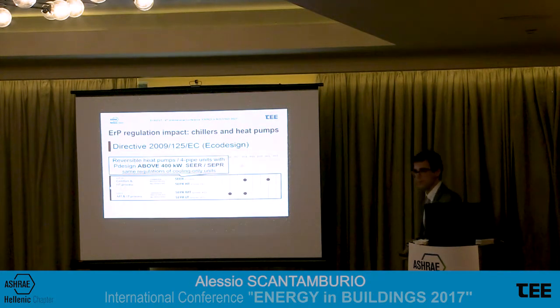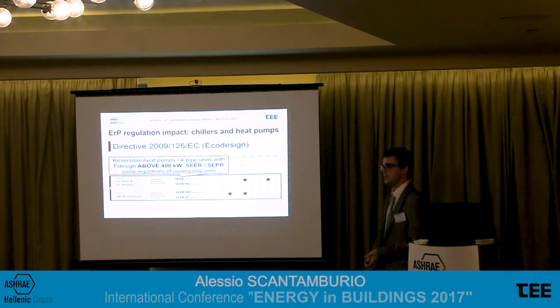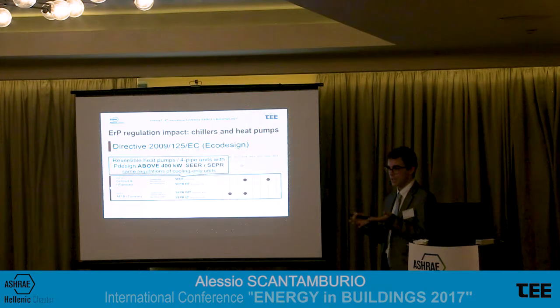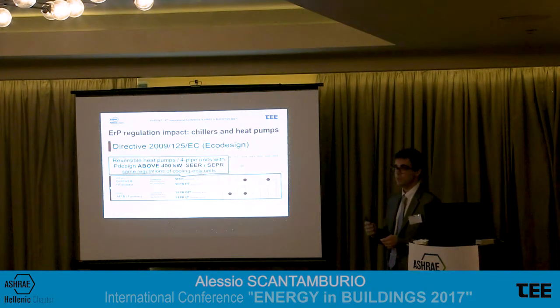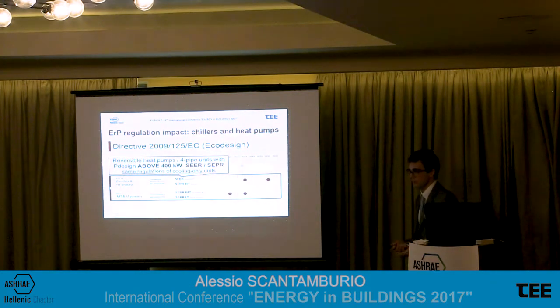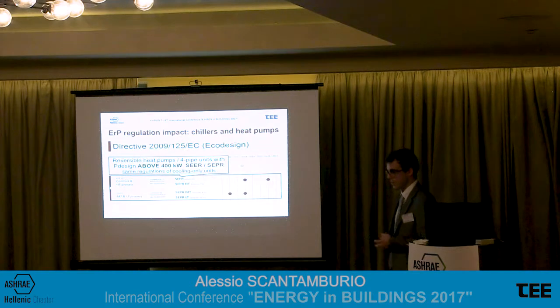And we are talking about enlarging the surfaces, using variable speed technologies, using additional devices to raise the efficiency, because we have to take into consideration that reversible heat pumps have at least one four-way valve inside the refrigerant circuit. So this means additional pressure drops. Additional pressure drops means less efficiency. And so always the same method of efficiency as in cooling-only units.